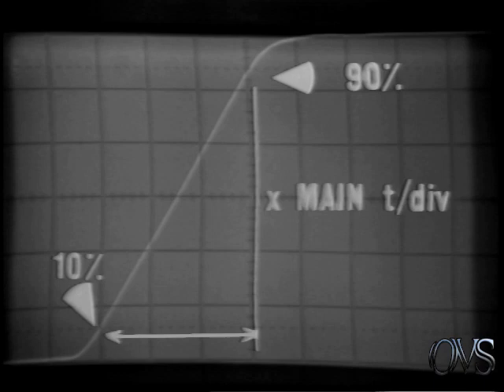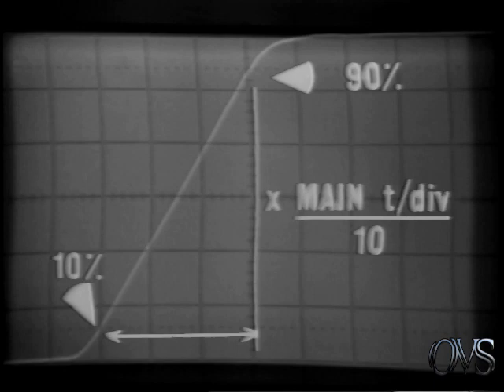For maximum measurement resolution, increase the sweep speed until the rise time interval is at least half the width of the display. If this is not possible, as in this case where we're using the fastest sweep speed, position the rise time interval to center screen and press the times 10 magnifier for improved resolution. Position the 10 percent point on the leading edge on a vertical line. Count the divisions to the 90 percent point and multiply by the main sweep setting. Since in this case the sweep is magnified, divide the result by 10.